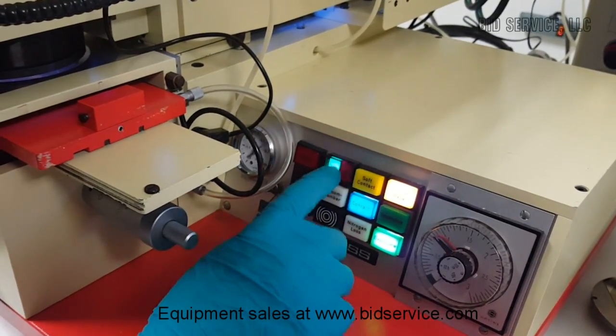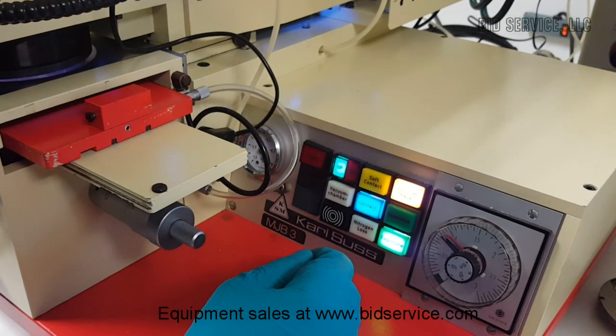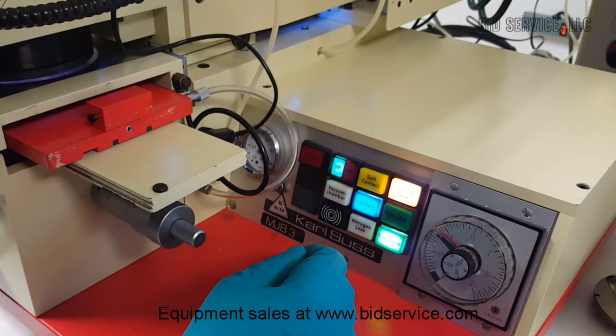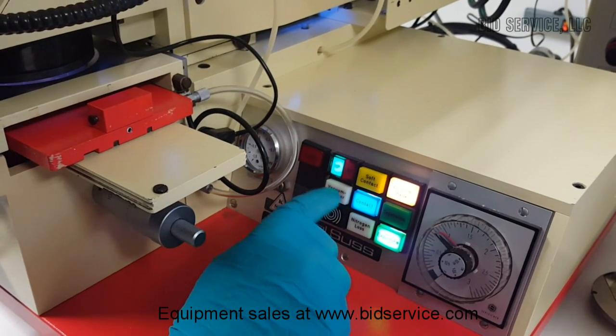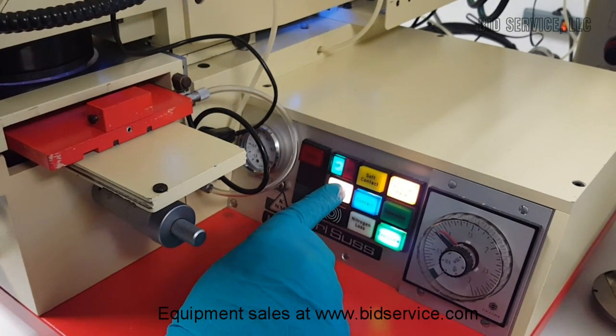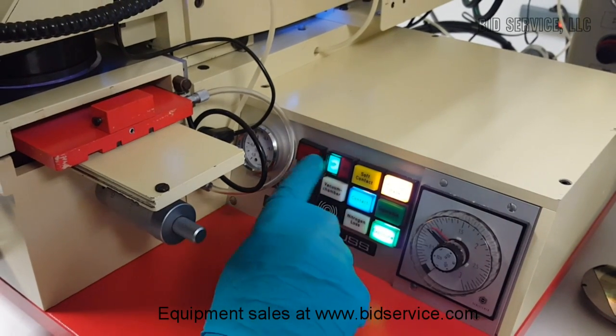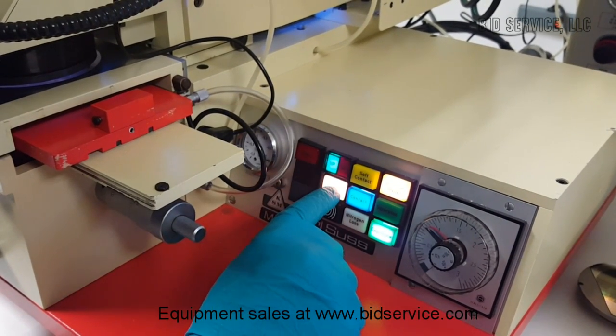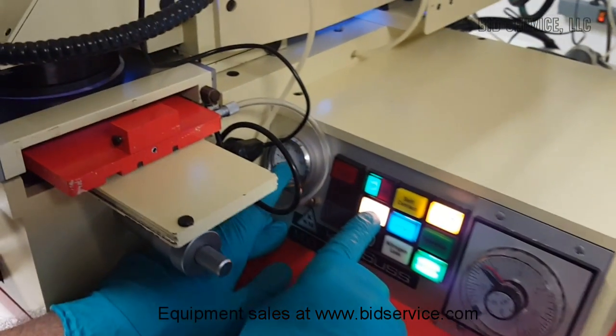In HP mode, there is a vacuum generated between the sample and the mask. When we press that button, the vacuum chamber reading can be seen here, which is adjustable using this regulator.